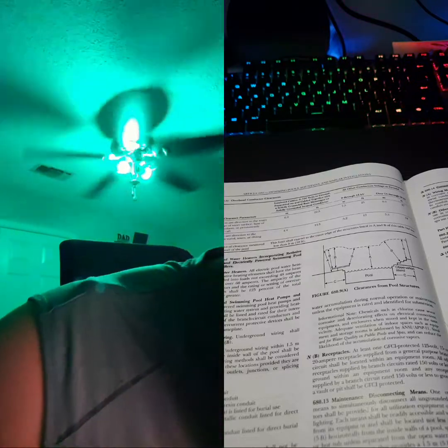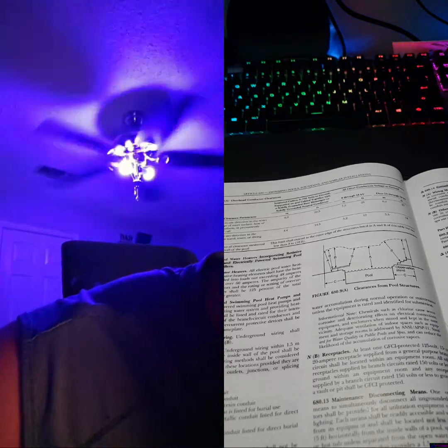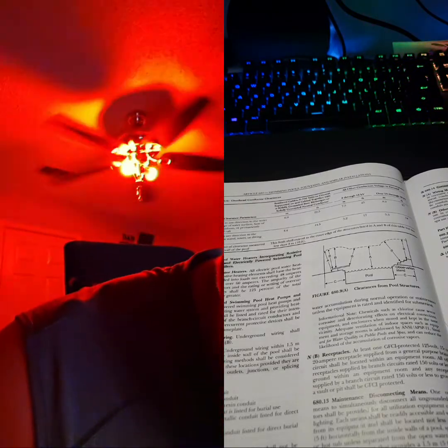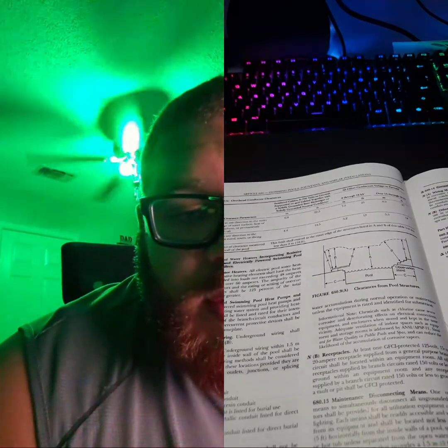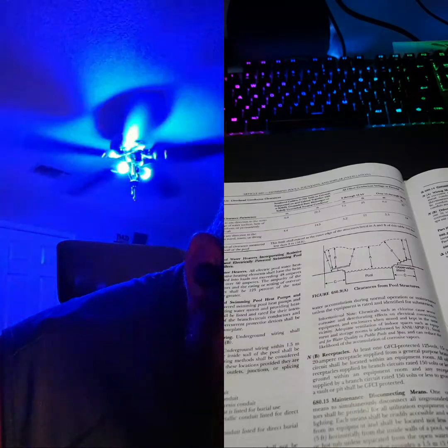And this is telling me overhead conductor clearances. Clearances in any direction. You see it? 0 through 15 kV. What's the voltage of the triplex? Does it say? 0 through 750. From water level is 22.5.